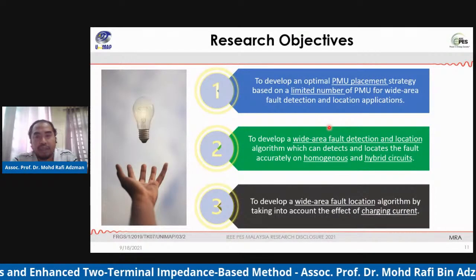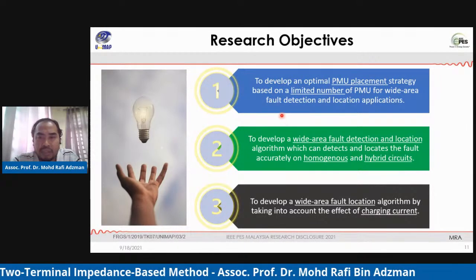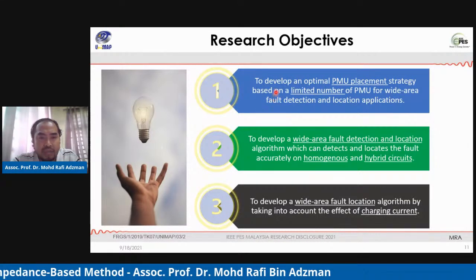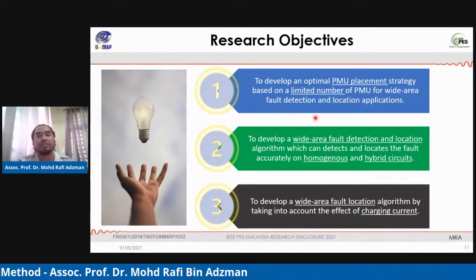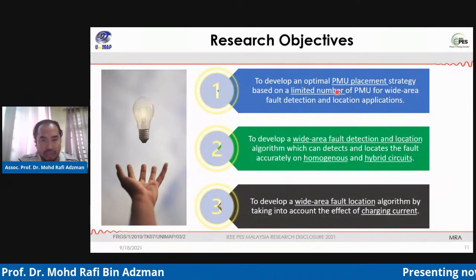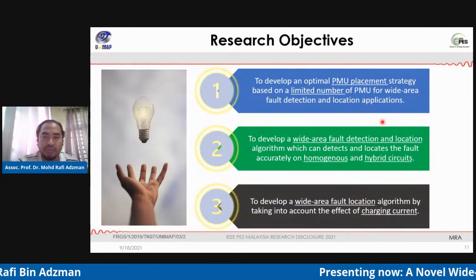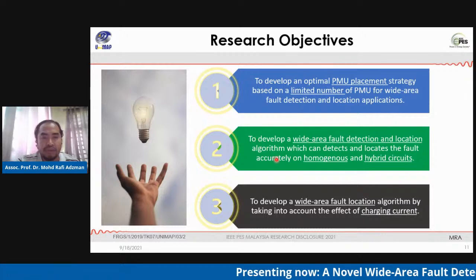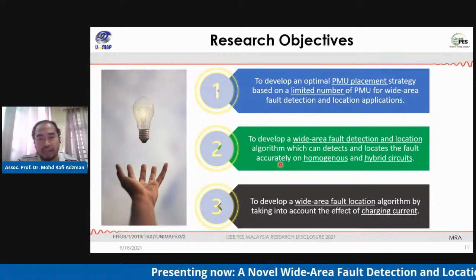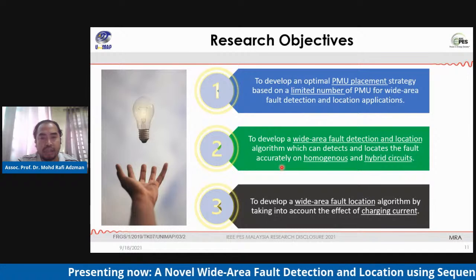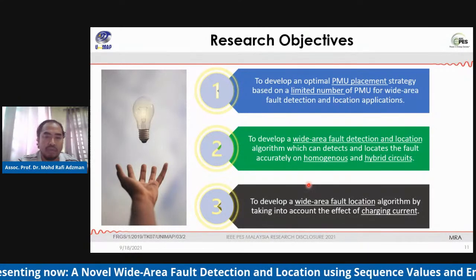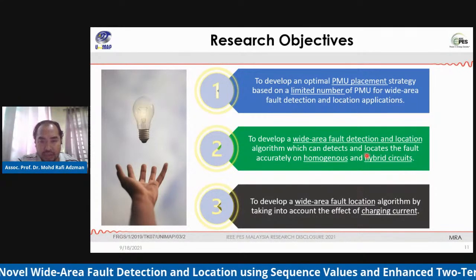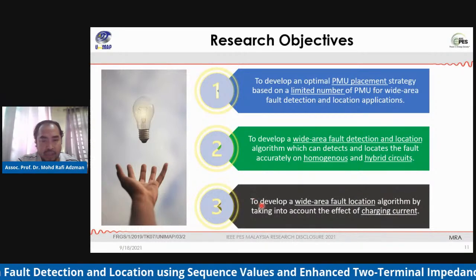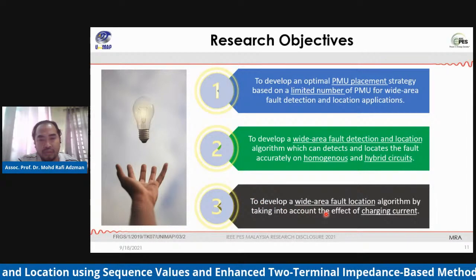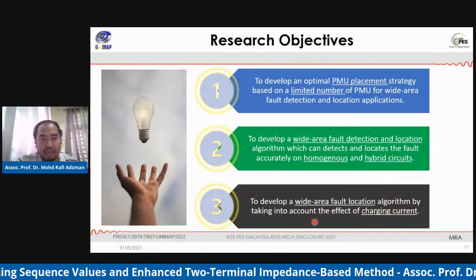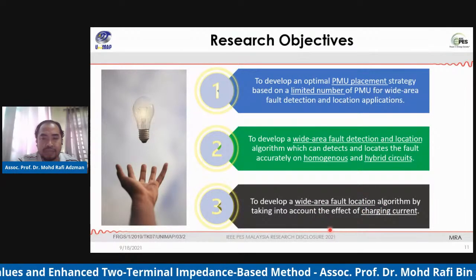Here, in this work, we have 3 main research objectives. The first one is to develop an optimal PMU placement strategy based on a limited number of PMUs. The second is to develop a wide area fault detection and location algorithm which can detect and locate the fault accurately on homogeneous and also hybrid circuits. And the third one is to develop a wide area fault location algorithm by taking into account the effect of the charging current.